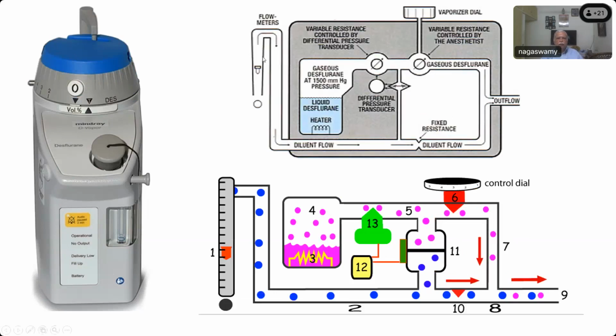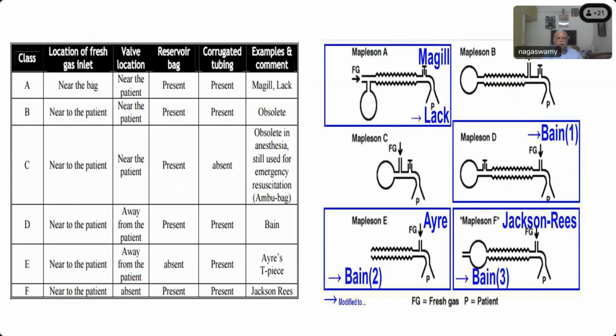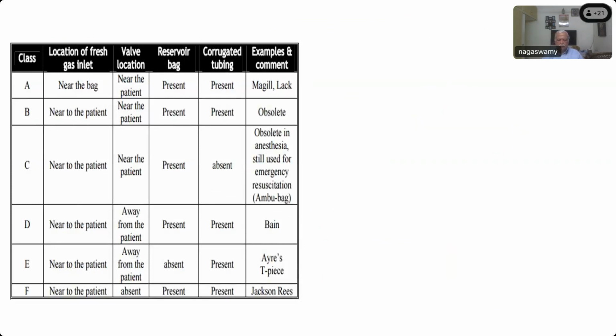So this is how the flow meter fresh gas flow is coming, and this is going directly into that, and you can see there are two resistors and all these things with variable resistance. So it is only the liquid which is injected into that and goes out. So you can see the gas does not directly enter the liquid chamber. Okay, only heated element. This heater vaporizes the desflurane, and that vaporized gas comes in here and then joins the fresh gas flow. And this is all about the circuit. So that is the main points. What we have seen is about the vaporizers.